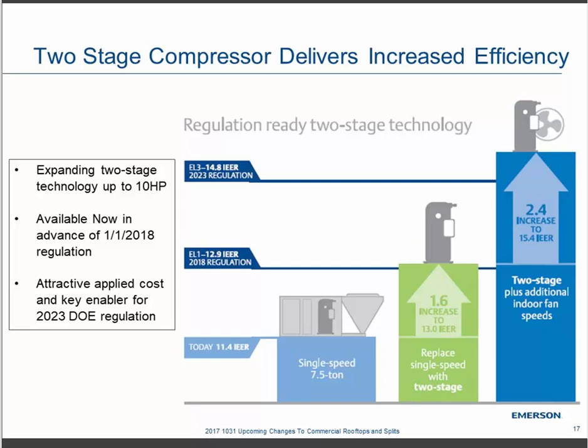This schematic shows that today's minimum efficiency for a seven and a half ton system is around 11.4 IEER. Our simulations show that dropping in the two-stage compressor can bump that up to hit the new 2018 regulation pretty easily. It also sets you up nicely for the 2023 regulation — just add variable speed or two-speed indoor fans, and you should be positioned well for that impending regulation.